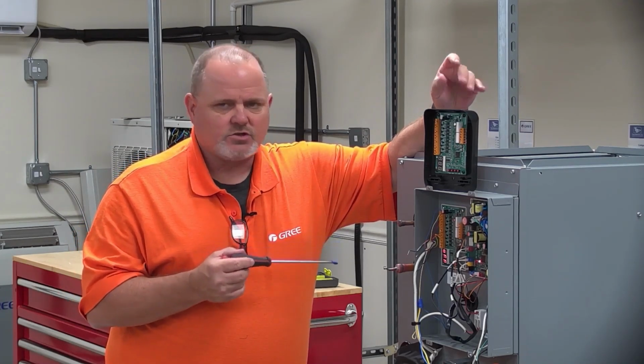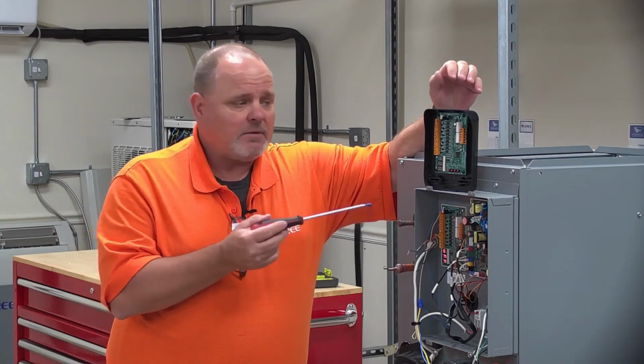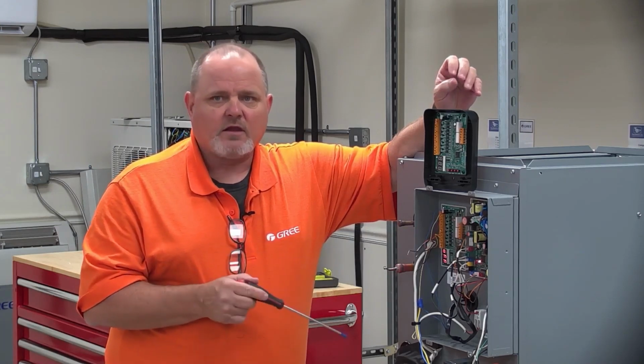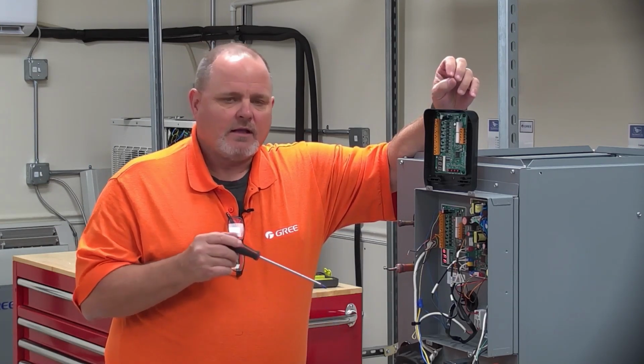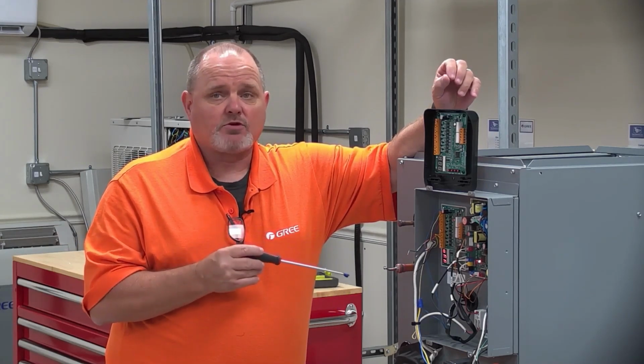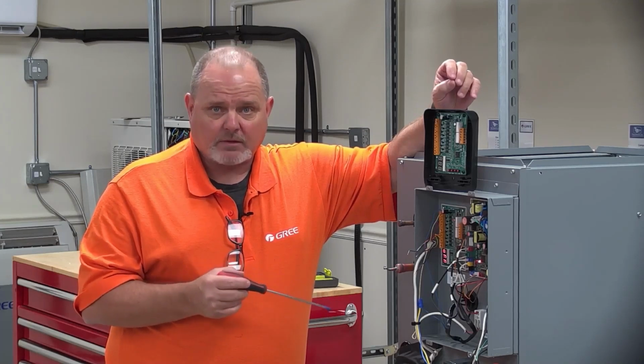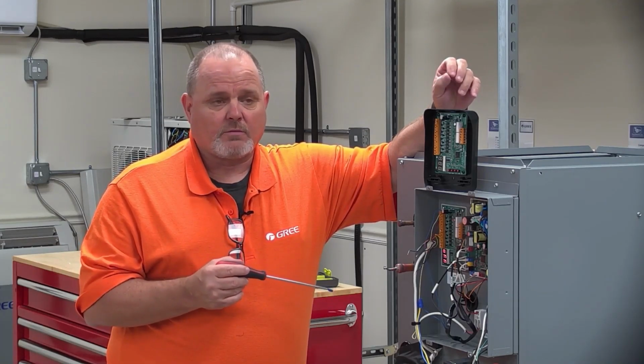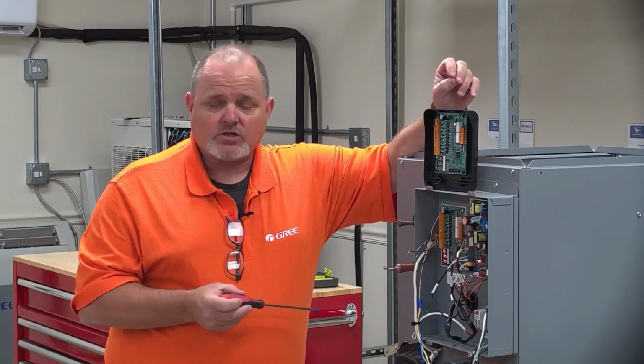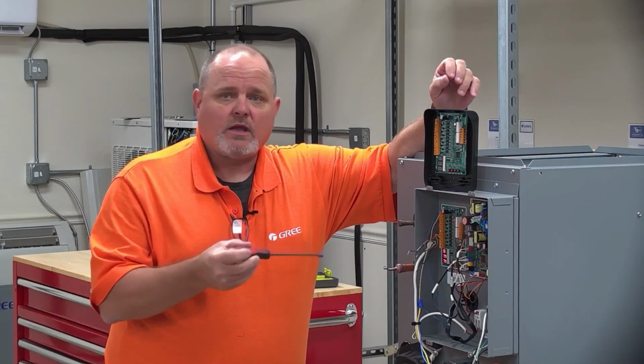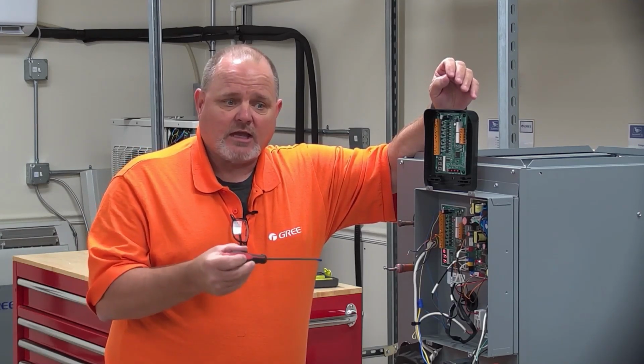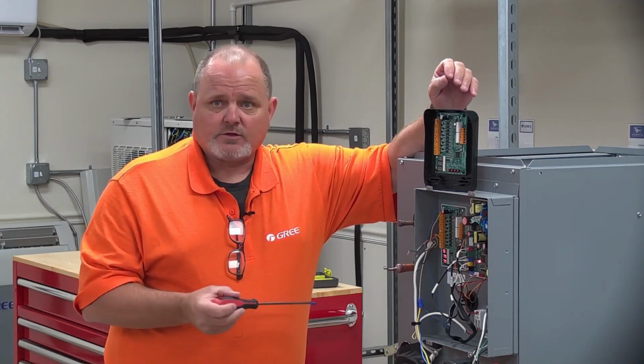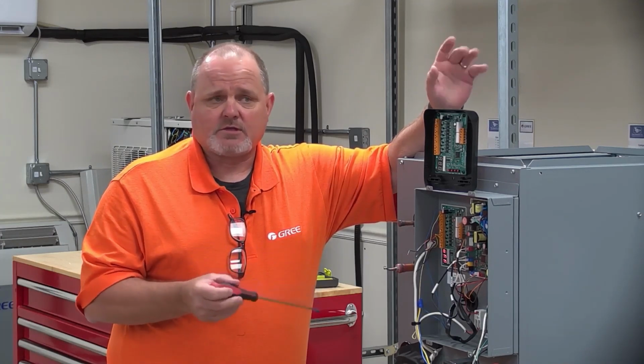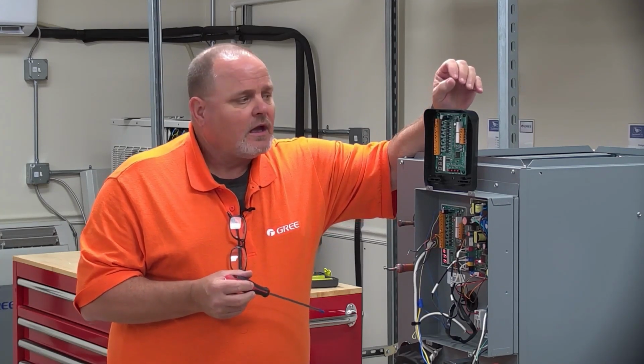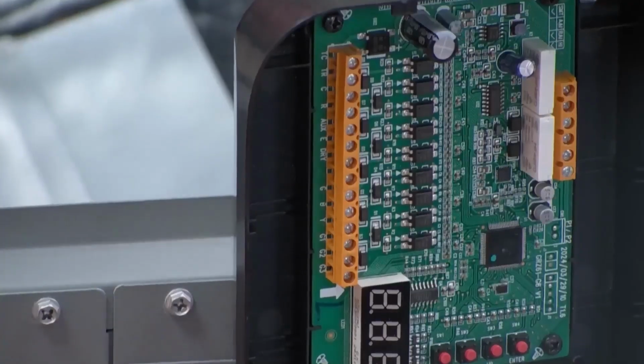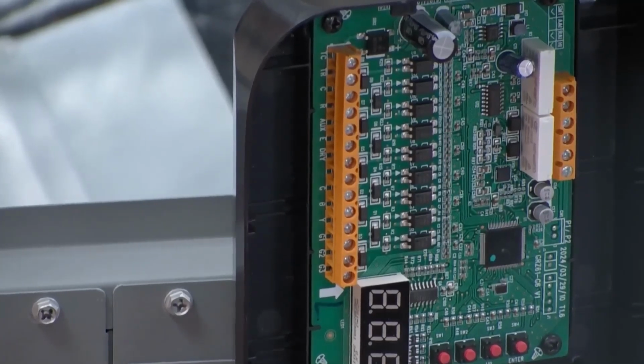Because your gas furnace connection, your W connection per se, is not coming to this control box at all. It's going directly to that furnace. So the only thing that's going to stop that furnace from running when the heat pump is running is that thermostat not letting that happen. Okay, so it's very important that you use a dual fuel capable thermostat and you set it up for dual fuel operation, letting that thermostat know in the setup that it has a heat pump with a gas furnace. Normally when you do that, the thermostats themselves will not send out a signal to both at the same time. Now, you have a G terminal on here as well. Again, you don't need to do that. Your G terminal will be going directly to your furnace.